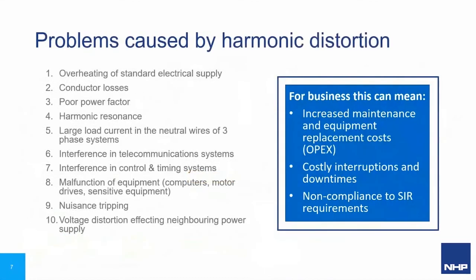Harmonics, as I said before, is the heavily distorted waveform that impacts the supply. Common causes of this are VSDs, LED lighting, and switch mode power supplies. It can cause a variety of issues, including overheating of standard electrical supply, conductor losses, poor power factor, harmonic resonance, and large load currents seen through neutral wires of three-phase systems. It also affects a lot of sensitive equipment, including computers, motor drives, telecommunication systems, and a lot of control and timing wires will experience some interference as well. It can also cause nuisance tripping and voltage distortion on neighbouring power supplies.